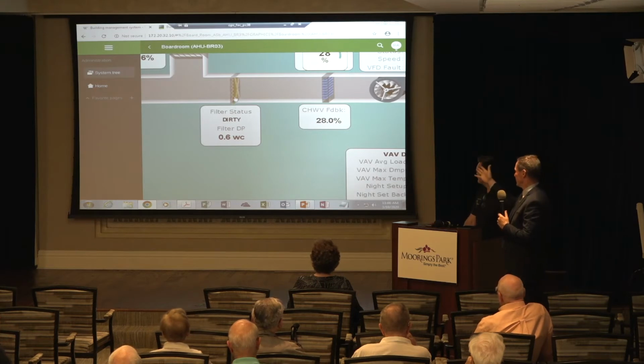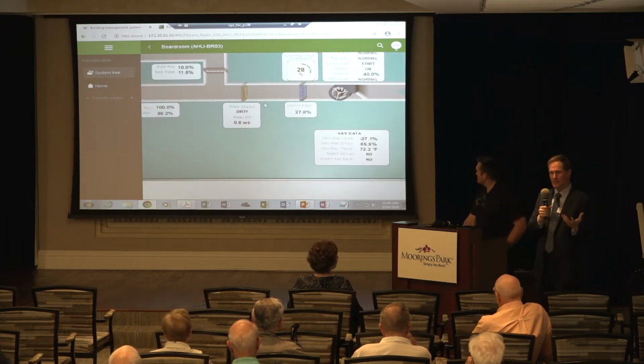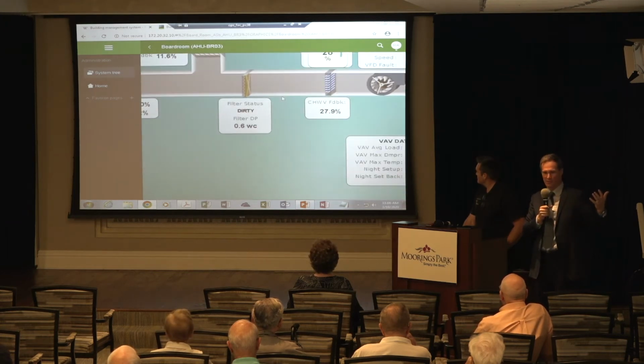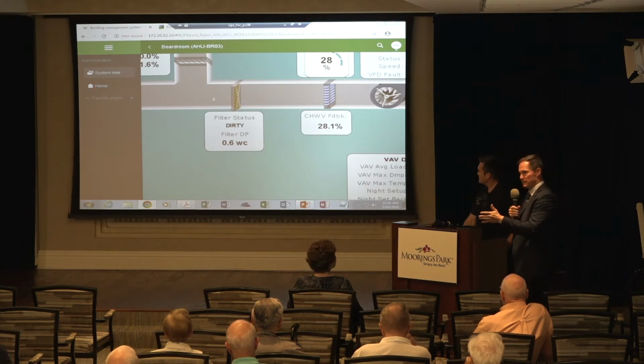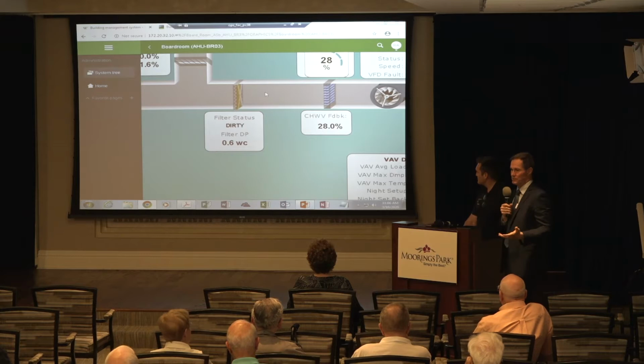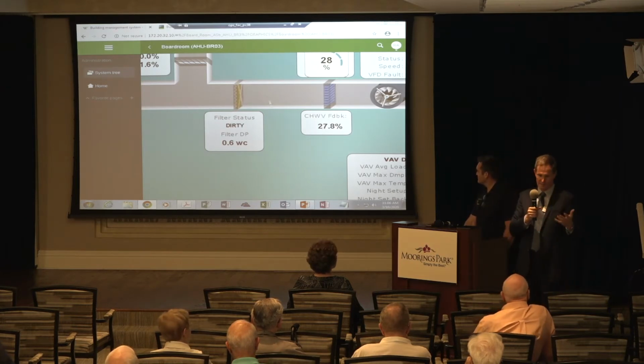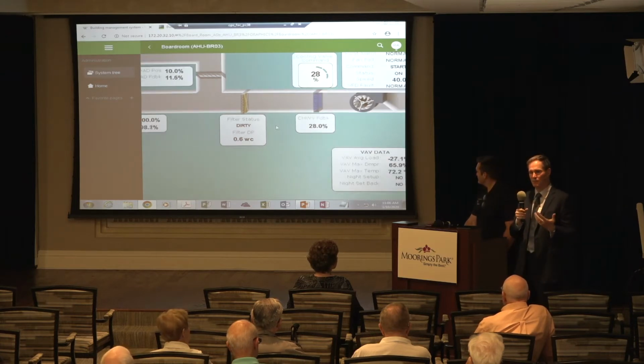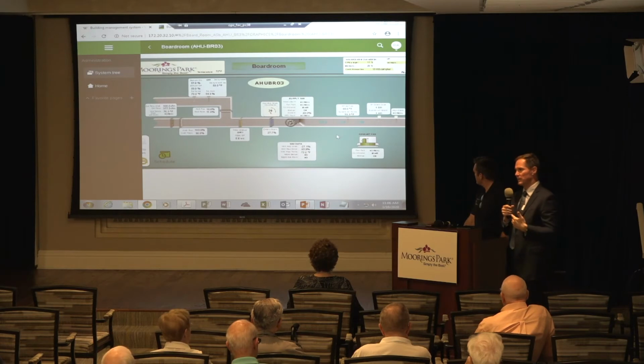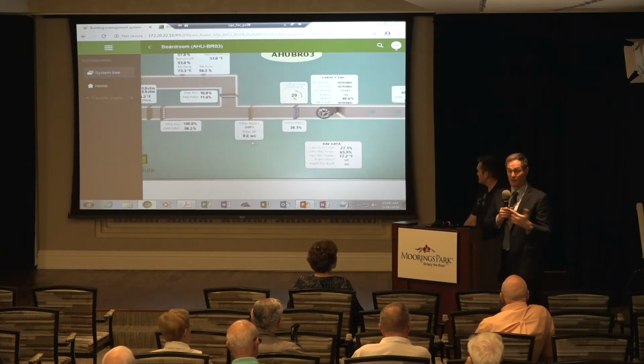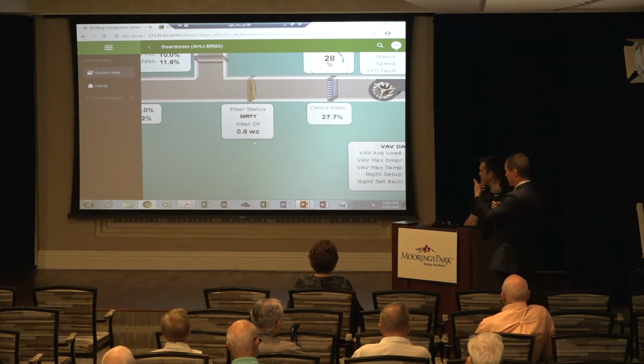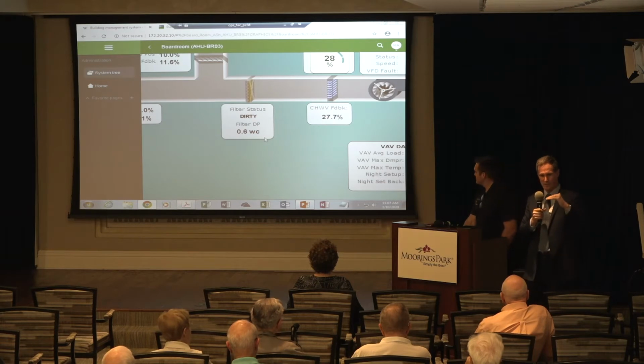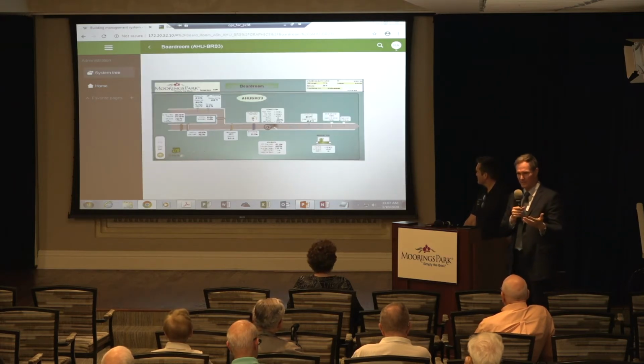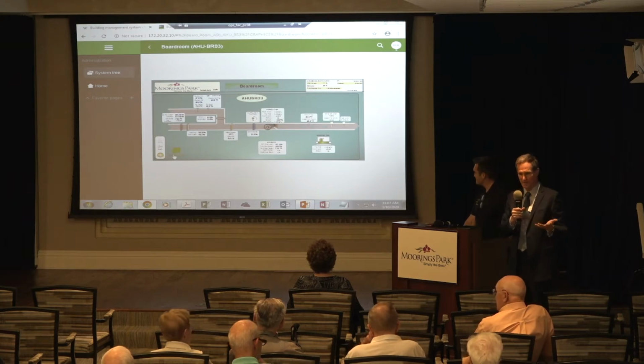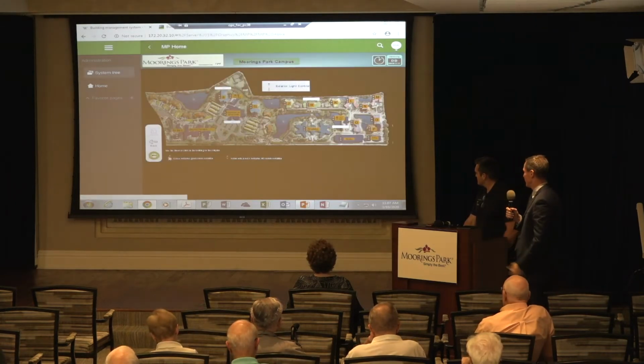So here's another item. Across a filter, we can detect a pressure drop. The pressure on the upstream side of the filter versus the downstream side can tell us if the filter's dirty. Now, how can we apply that? Well, one, it's nice to know when the filters are dirty, but the other way is something we call predictive maintenance. Rather than the maintenance folks going in there every quarter and changing that filter whether it needs it or not, we can set parameters. So if it has 0.6 inches of water column pressure across it, then we can change the filters based on a condition. That's what they call predictive maintenance versus preventative maintenance.